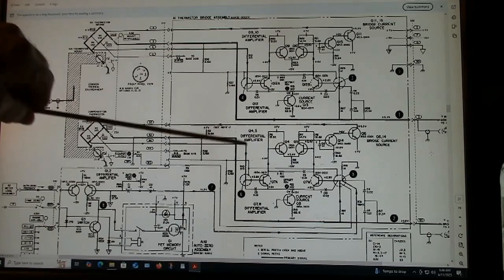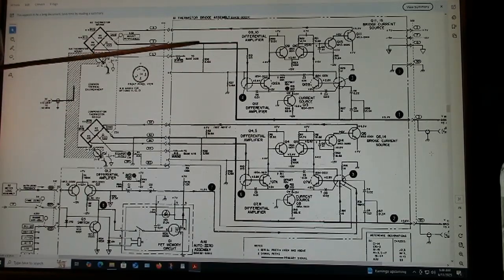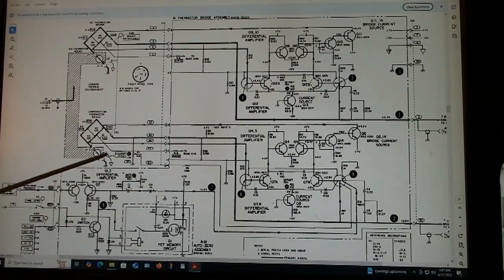And all of this circuitry here, all this does is maintain a balance in the bridge. In other words, as these resistances change, it will change the bias voltage on each bridge circuit to maintain a similar output. So when you first set this device up, you're not applying any RF. You adjust the coarse zero here to balance the bridge. So with the bridge balanced, the outputs will be the same.